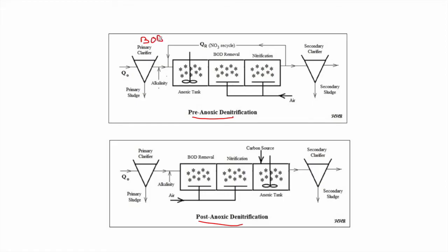For pre-anoxic denitrification, the carbon source needed for denitrification comes from the BOD in the primary clarifier effluent. Since the BOD removal tank comes after, the BOD concentration is still high — around 70% remains after the primary clarifier removes about 30%. However, we do need to add the nitrate nitrogen (NO3) produced by nitrification, so we recycle and pump water back from the nitrification tank into the anoxic tank.